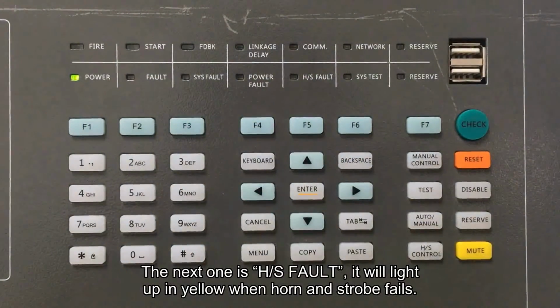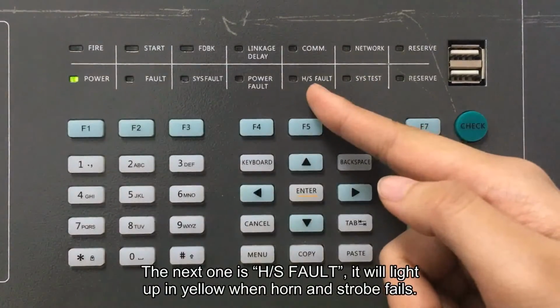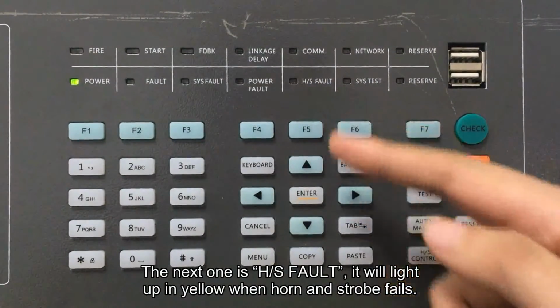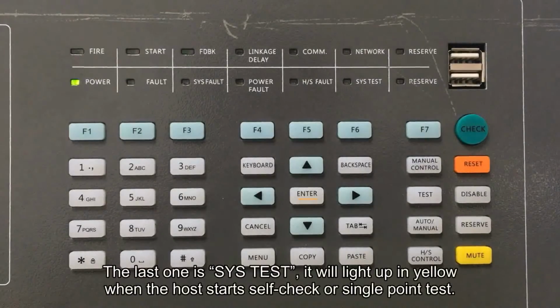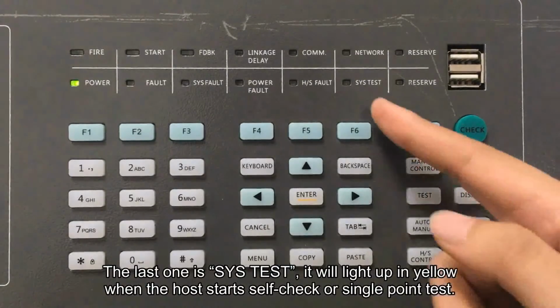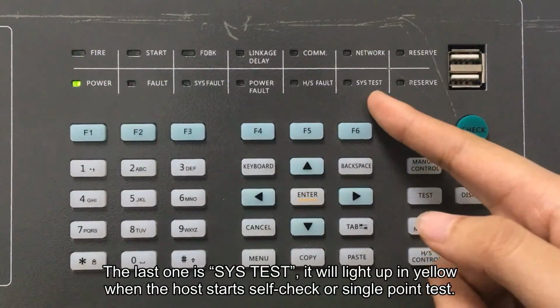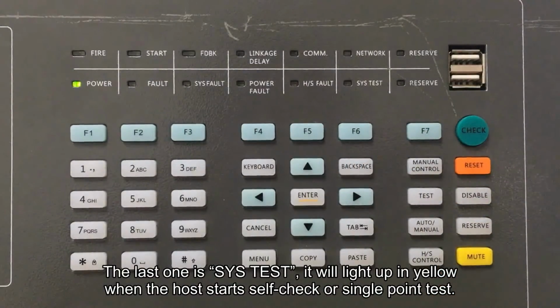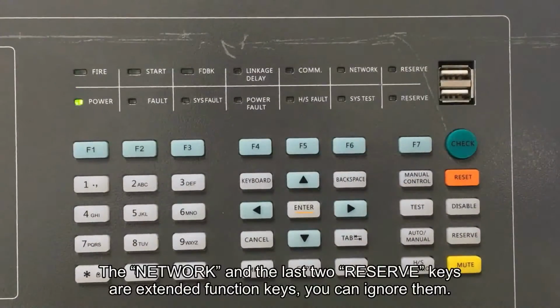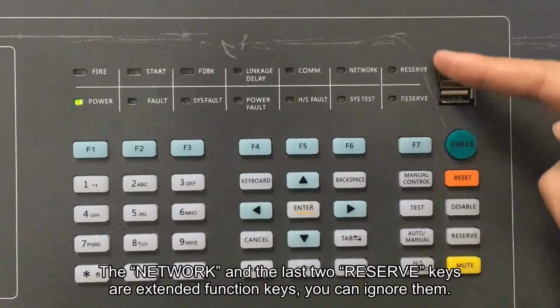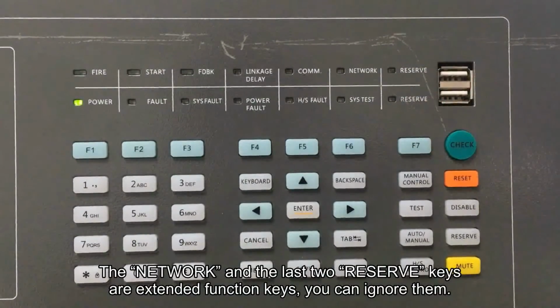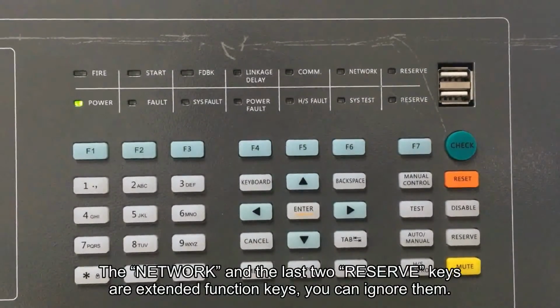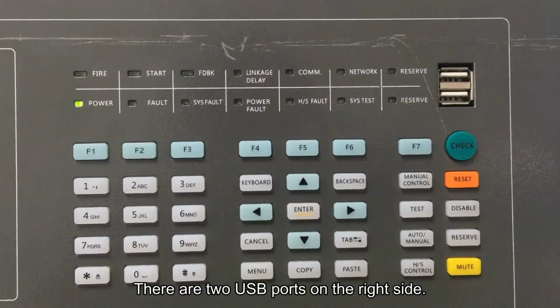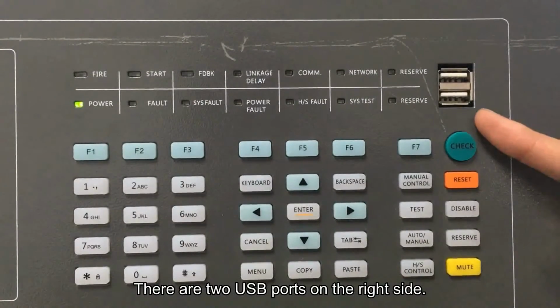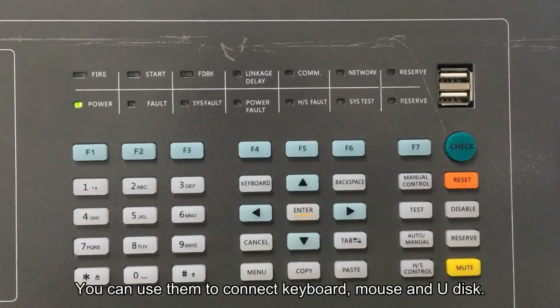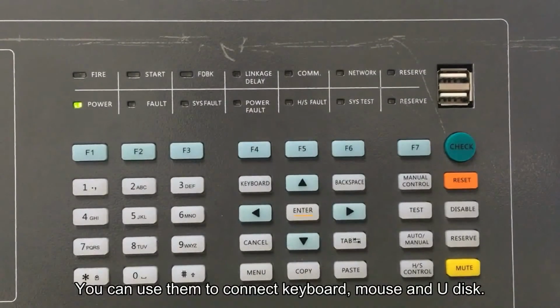The next one is H/S FAULT. It will light up in yellow when horn and strobe fails. The last one is sys-test. It will light up in yellow when the host starts self-check or single-point test. The network and the last 2 reserve keys are extended function keys. You can ignore them. There are 2 USB ports on the right side. You can use them to connect keyboard, mouse, and U-disk.